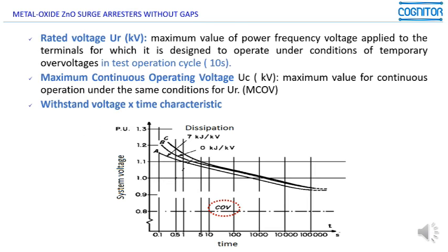The main concept of the use of surge arresters is relatively easy to understand. We have one element that is something like a resistor that should be near to an infinite resistance before the arrival of a surge or an overvoltage, and should become practically zero resistance when a steep overvoltage arrives.